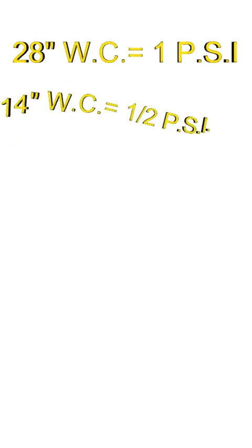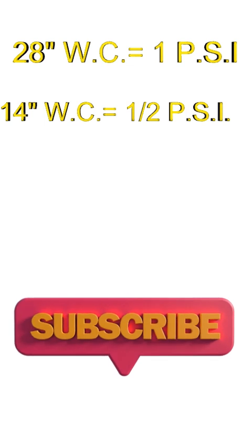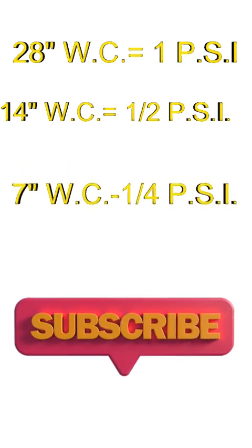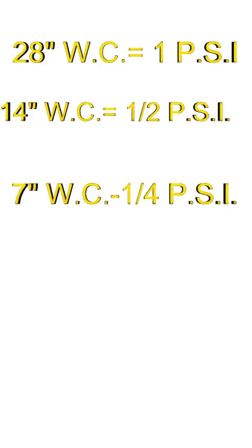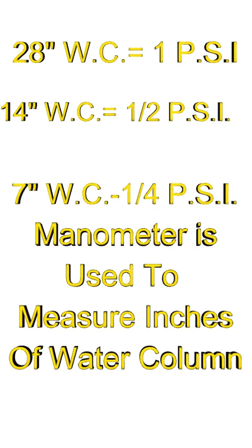We could also say 14 inches of water column equals a half psi, 7 inches of water column equals a quarter psi. And the manometer is used to measure low pressures such as used in gas installations. So I hope this helped you understand this and there will be more of this to come. Talk to you soon.